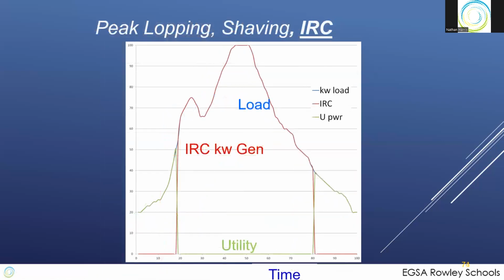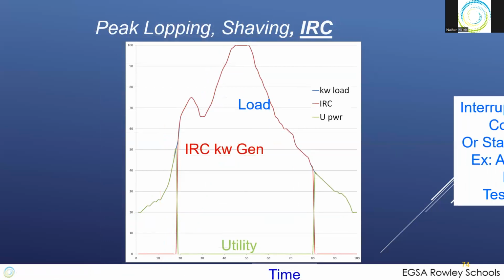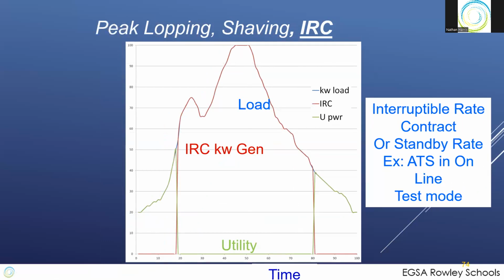IRC is called interruptible rate contract. An example of this would be a standby rate or ATS and load. You go to the utility and say, what are your IRCs, or what do you offer for that? And they'll say, okay, if you agree to let us take you offline in times of constraint, if our grid gets stressed, we'll take you offline for a max of 4 hours, for a max of 10 times a year or something. And at that point, they'll send you a signal that says, okay, get offline. You start your gens, you take over your load.